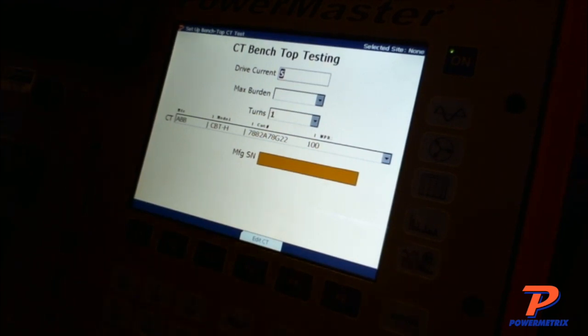And now here's where I select how much I'm going to drive. So everyone knows I've put 5 amps through my source, my other 7 series on the floor. I'm running 5 amps right now through these 200 to 5 CTs, which, well, this is a 400, excuse me. That's not nearly enough, right? You want to be at least at 10%, okay?